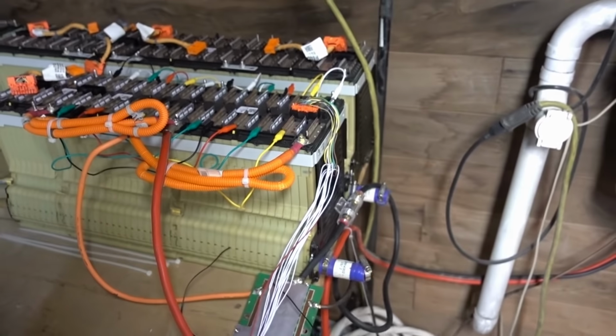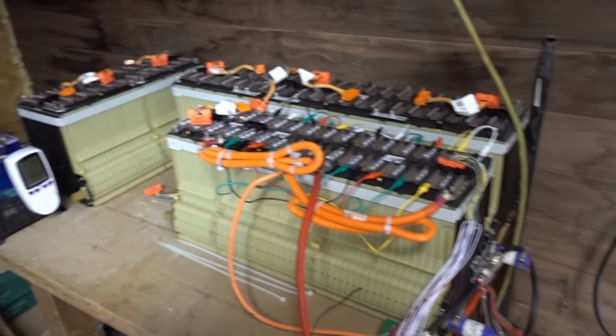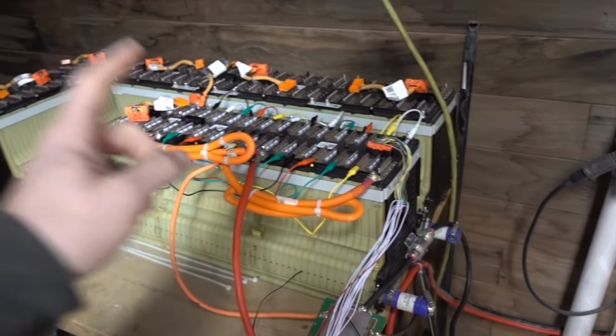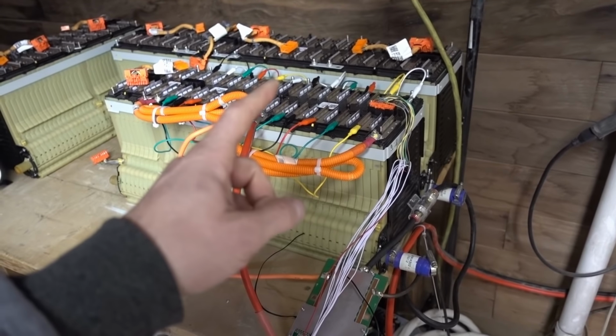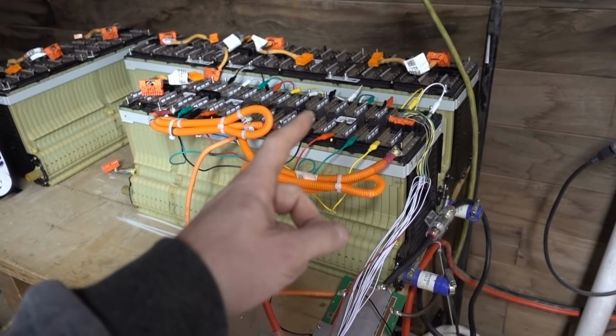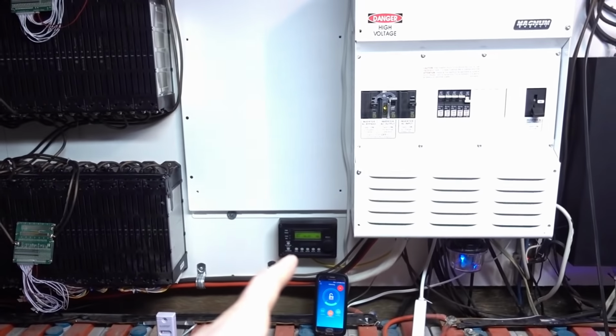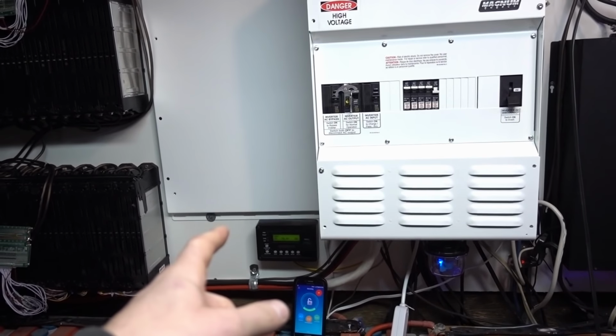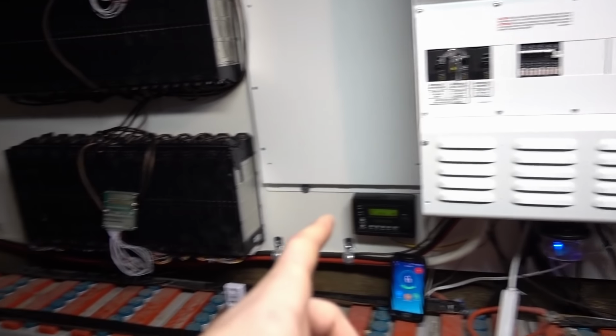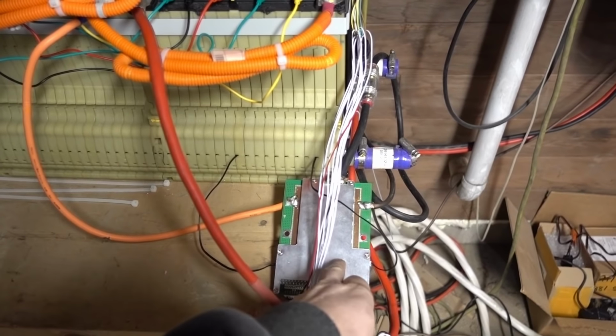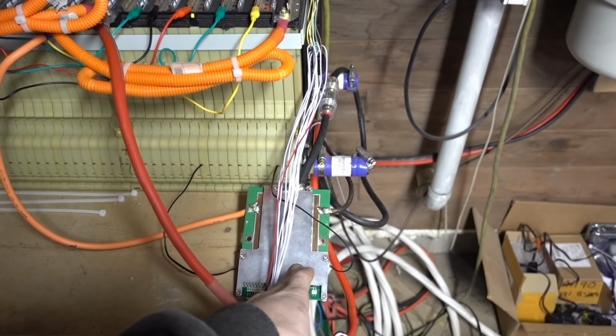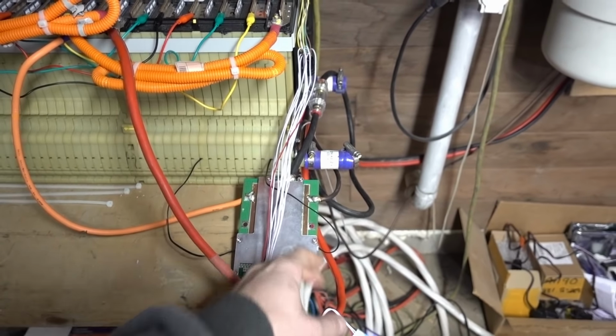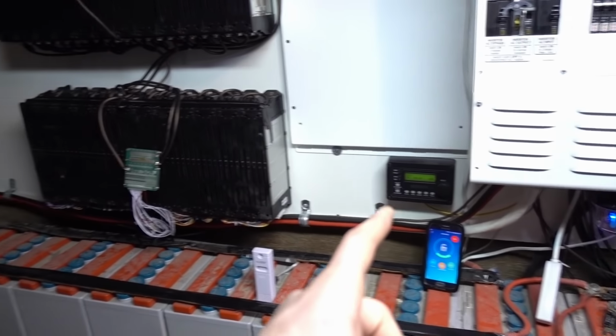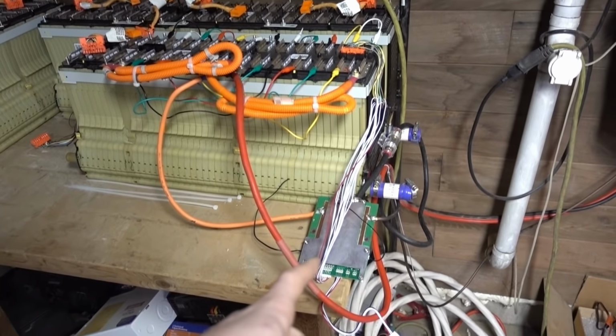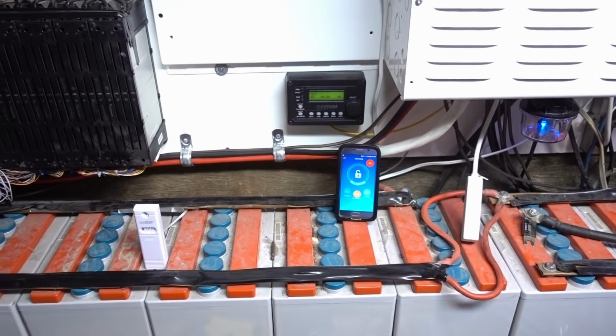I think that'll be like 30 or 40 amps, something like that. But yeah, we're going to see what kind of capacity we get out of this battery. I have it set to cut off - I think the inverter will shut off at 38.8 volts, and these are set to shut off at 3.1 volts per cell, I believe. So I'm pretty sure the inverter is going to kick out before the BMS does. That's good, and I'll get back to you guys.